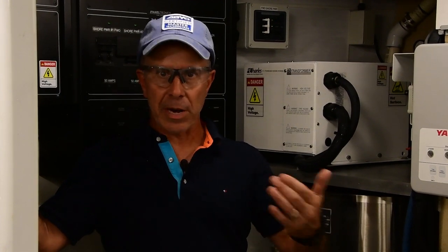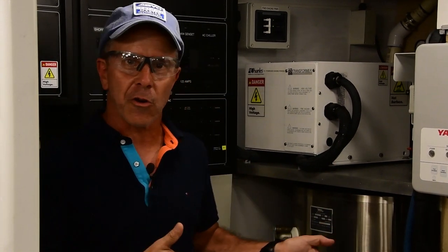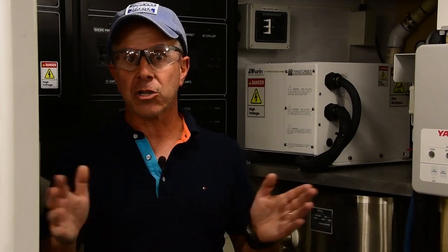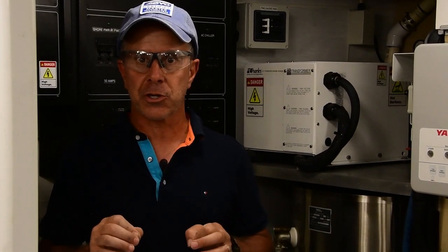Another option for transformers of the 240 volt variety, if your inlet is 240 volts, you can specify the option of having a 120 volt primary or 120 volt inlet on that transformer, again as an option. When would you use that? Well, if you came into a dock that only had a 120 volt shore power pedestal outlet available to you, you'd be able to plug into that. The transformer would convert that 120 to 120/240, again split phase on the boat. It could energize, therefore, anything on the boat, but not everything, because you'd be running at a lower overall wattage, but you still could choose what you were going to run on the boat. You wouldn't be dead in the water with the inability to plug in altogether.